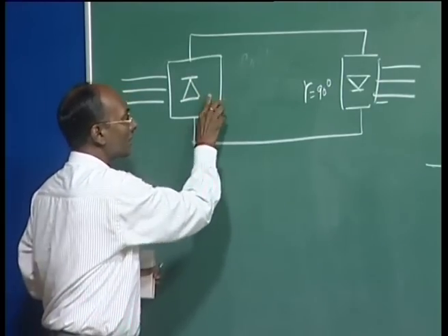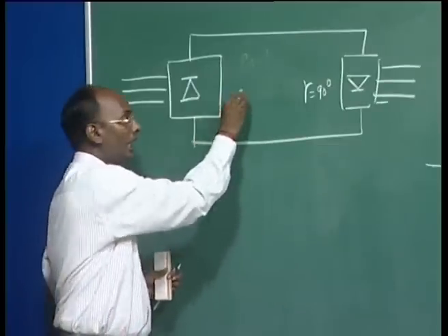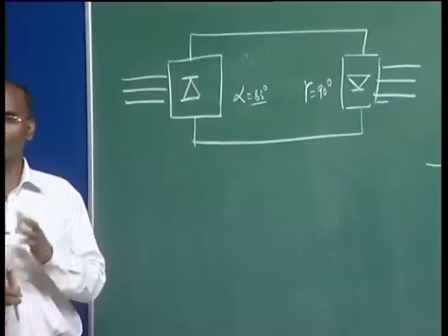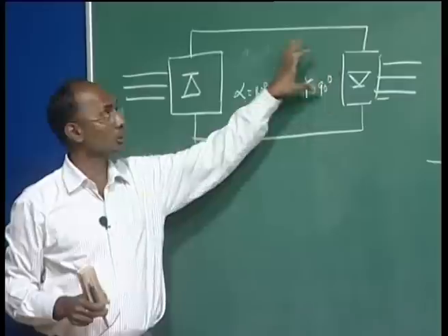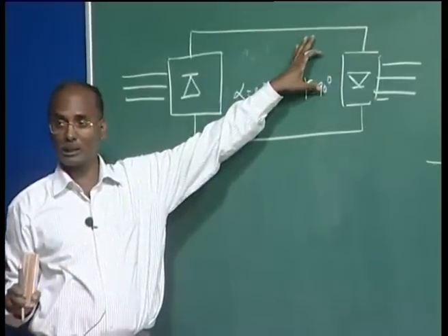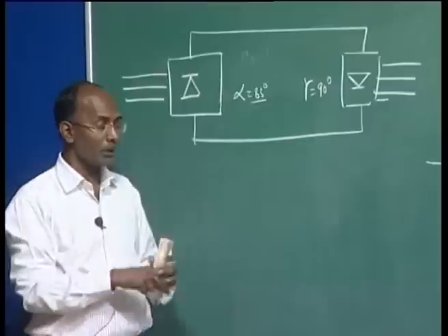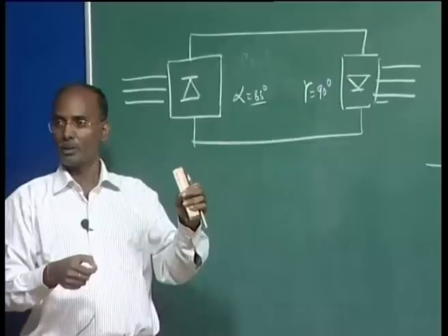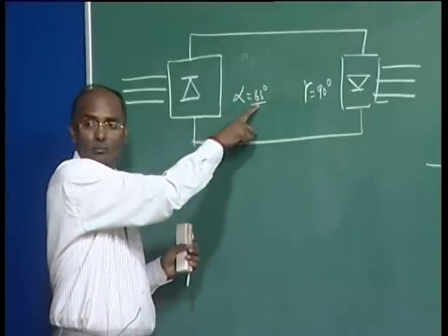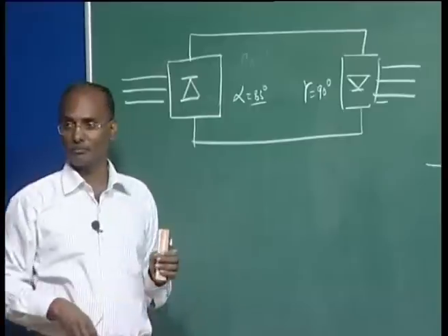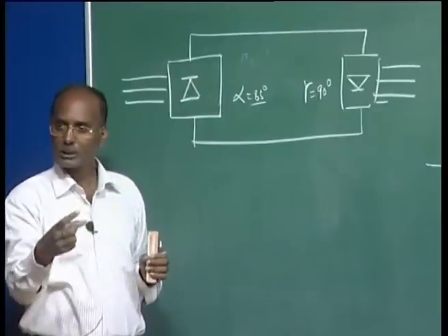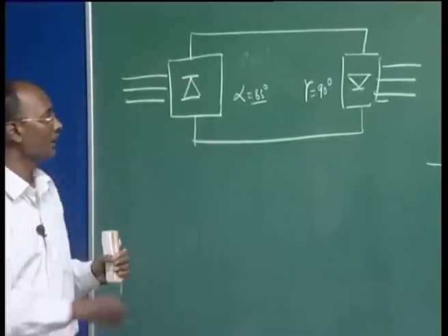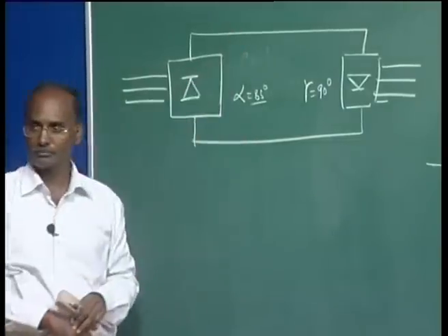Now, in this case, you have to deblock this rectifier and give alpha as 85 degree. We are not giving 90 degree because there will be some U. Once this is on, no current is flowing here, so U is not applicable at all, because it is simply VD = VDO cos gamma. So, the gamma is 90, VD is 0. Now, if you give 90 degree here, what happens? Due to U, even this voltage may be negative. So, we try to give some positive voltage, we try to ignite somewhere around 85 degree or so, and still this voltage is very, very small.